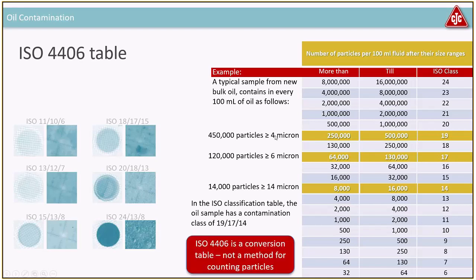What this table doesn't tell you is how you got the numbers — whether by laser particle counter, pore blockage or flow decay method, or membrane. You can only compare numbers if you're using the same technology. Using different labs, you will see a difference in ISO counts — a class 19 in one lab could be 20 or 18 in another. Every time you increase one class number, you're actually doubling the particle count.